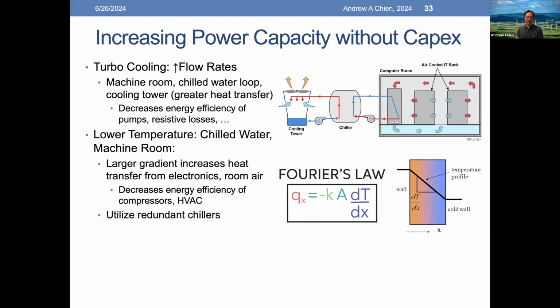You can do more. You can lower the temperature. It's become popular to run data centers with hot water and hot air, and that does increase energy efficiency. But if we increase this gradient, that is, we run with cooler water and cooler air, we can actually increase the heat transfer capacity without increasing the CapEx of the system. We just drive these systems at a higher rate. Yes, it decreases the energy efficiency of the compressors and the HVAC, and we can utilize redundant equipment we have for just reliability and so on. We can probably increase the capacity, I would say easily by 20 to 30%, if not more, without much increase in CapEx. Why haven't we done this in the past? Again, we've been worshiping at the altar of energy efficiency, and that turns out to not be the most important thing in this dynamic world.